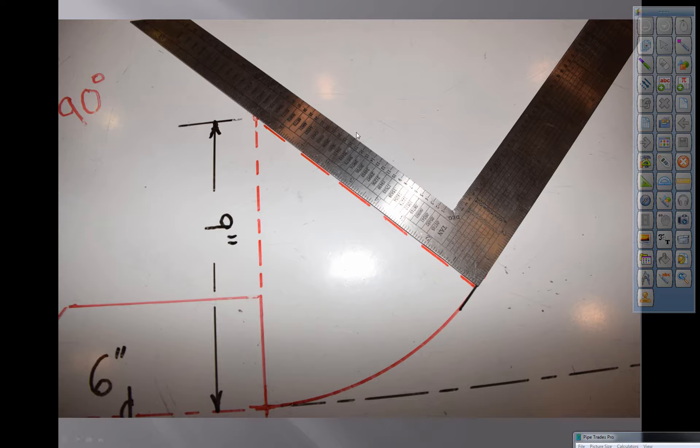Because the six inch elbow has a radius of nine inches. So bring that square down the black center line. When that nine hits the vertex, you nailed it.